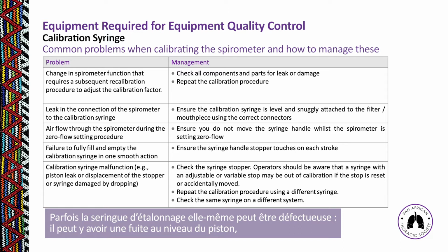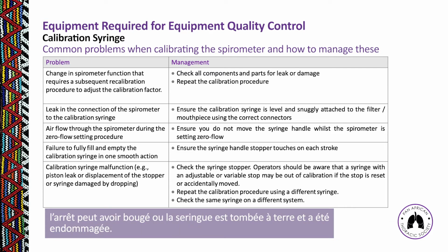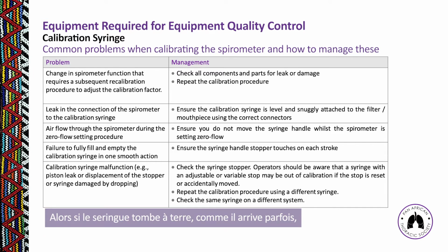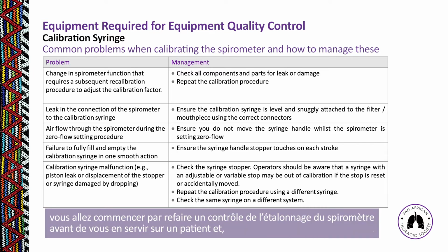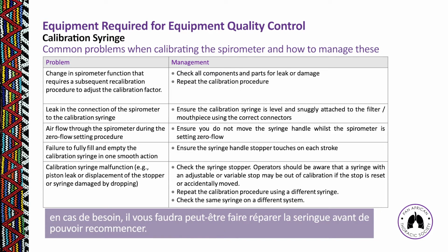Sometimes a calibration syringe can malfunction, so there could be a problem with the piston leaking, displacement of the stopper, or the syringe could be damaged by dropping. If the syringe does somehow manage to get dropped, it does happen at times, the first thing you're going to do is recheck the calibration of the spirometer before you use it on a patient. And if necessary, you may have to get the syringe repaired before you can go forward again.